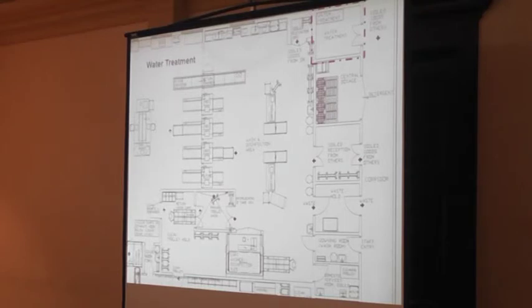The water is too hot. Okay. We need to have other ones. So making a water sample is highly recommended to guarantee the result. This is a very common problem in the world for CSSD, that we need to check before we create this nice CSSD.